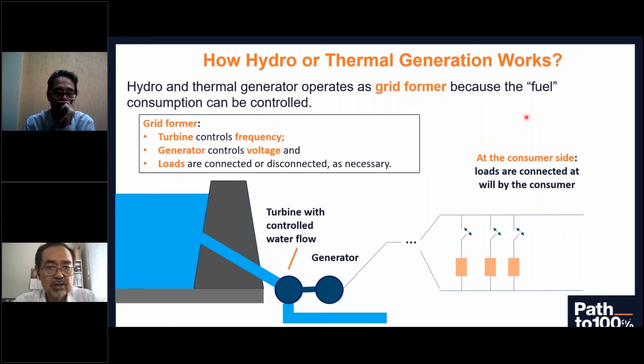So I think it's important to take care of this connection. But before explaining how we can do this connection, it's important to give some concept on how hydro and thermal generation works. Normally, when you have a hydropower plant, you have water, you have the turbine, and controlling the water flow means you're controlling the fuel. You can control the turbine speed, which means you control the frequency, and the generator controls the voltage.